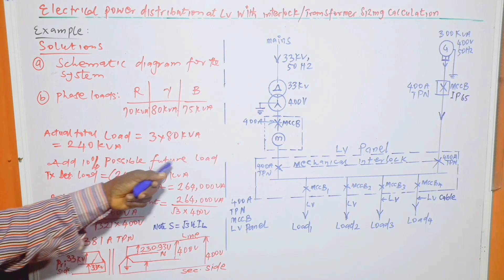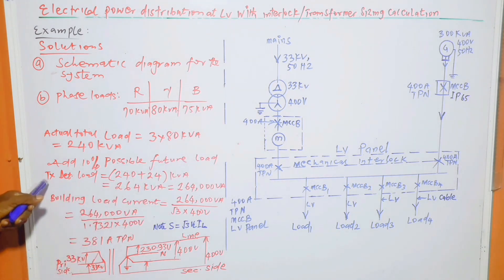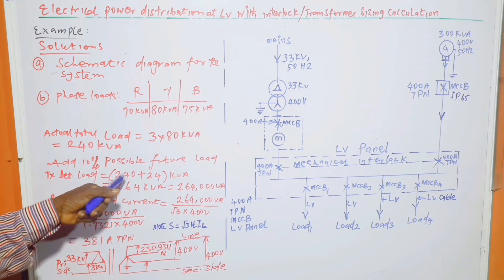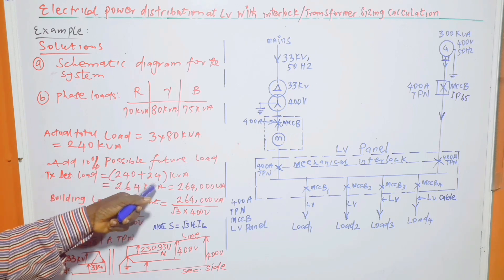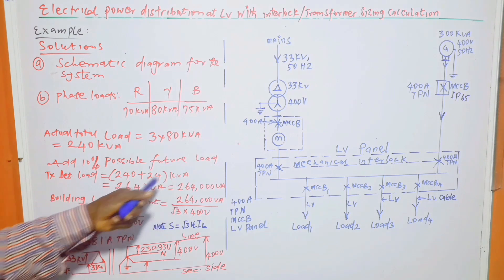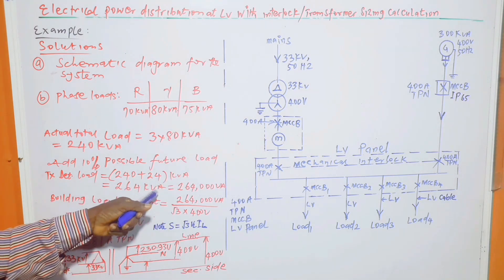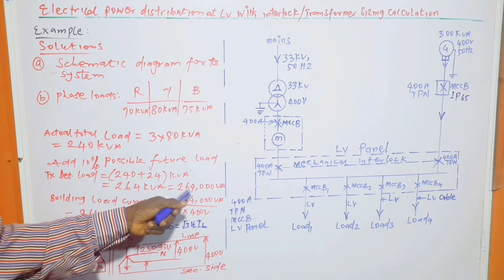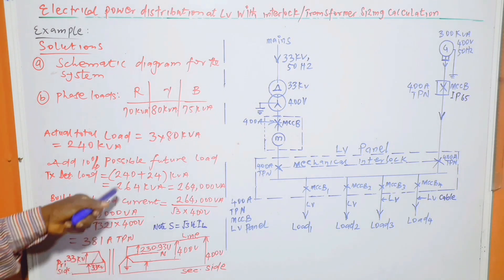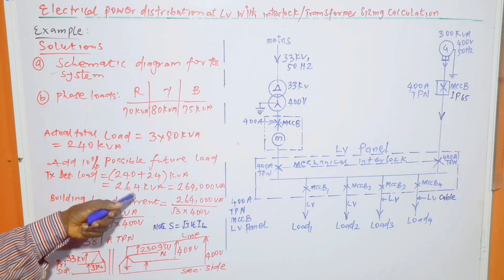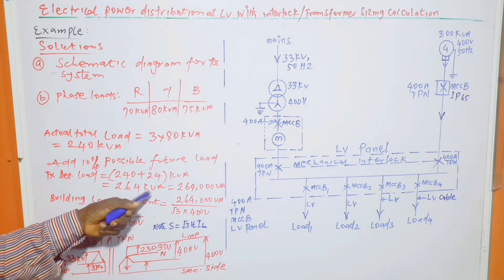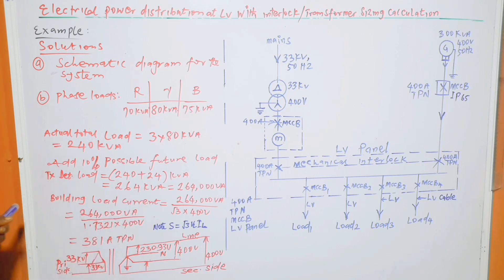Now, add 10% possible future load, then transformer rating determining load is equal to 240 plus 24 kVA, which is equal to 264 kVA, or 264,000 VA. So this is the building load, 264 kVA, which is the answer to the B part.